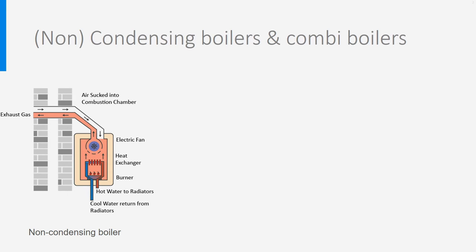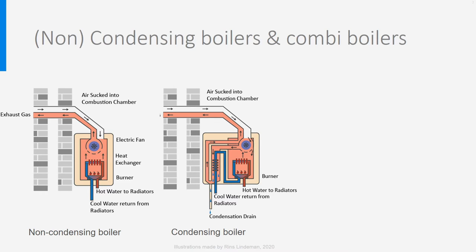In a condensing boiler, an additional heat exchanger is placed — here on the left of the burner — and the fumes, which contain a lot of water vapor, are directed to this heat exchanger. They give their heat to the cold return water before flowing outside. Not only the fumes give heat back — mainly the water vapor contained in the fumes gives latent energy that is released when the vapor cools down enough to condensate. These droplets of condensed water must be drained out through an additional pipe. With this condensation, much more heat is recovered from the burning process.